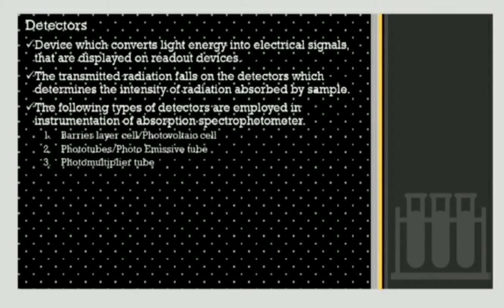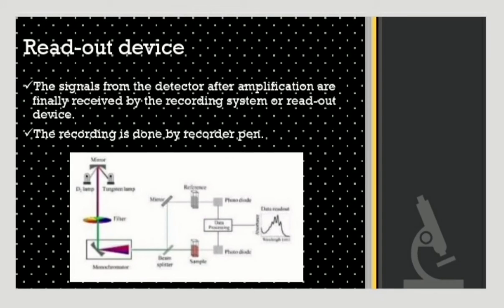The next instrumentation component is the detector — devices which convert light energy into electrical signals displayed on readout devices. The transmitted radiation falls on the detector, which determines the intensity of radiation absorbed by the sample. Types of detectors include the barrier layer cell (also known as the photovoltaic cell), photo tubes, photo emissive tubes, and photo multiplier tubes. The readout device is the final component; signals from the detector after amplification are received by the recording system. Recording is done by a recorder pen. This diagram shows the instrumentation of the complete UV visible spectroscopy setup.